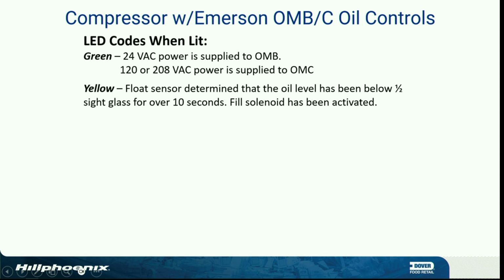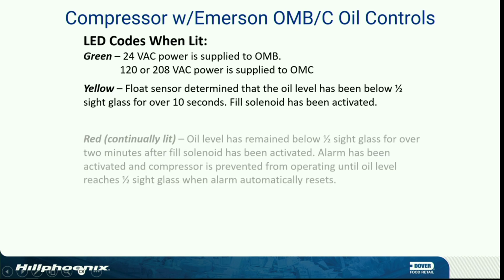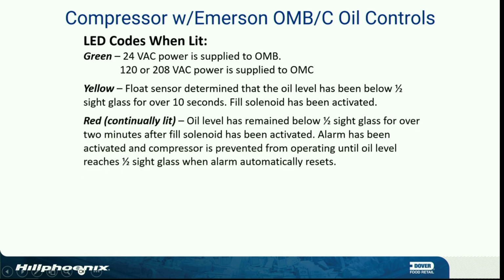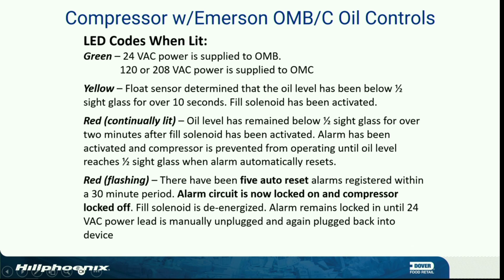But it will recycle 5 times. Oil level has remained below that half sight for over 2 minutes after the fill solenoid has been activated. Alarm has been activated and the compressor is prevented from operating until the oil level reaches half. The alarm automatically resets 5 times. Red flashing: there have been 5 auto resets registered within a 30-minute period. Alarm circuit is now locked on and the compressor is locked out. And how do you reset that? Power cycle.